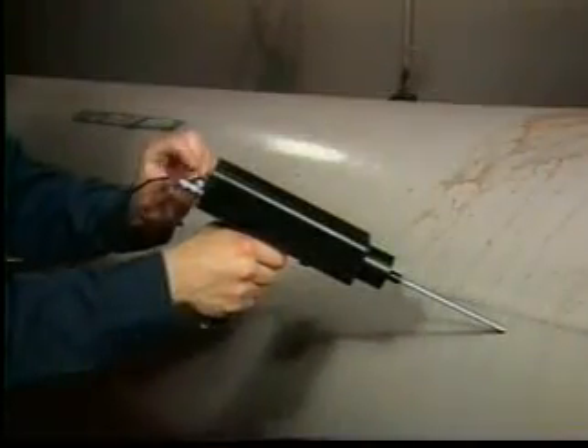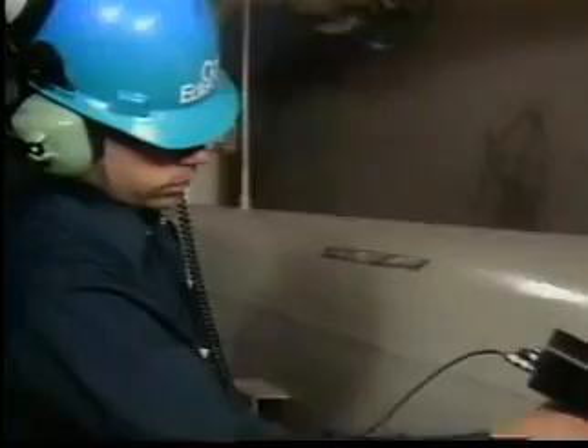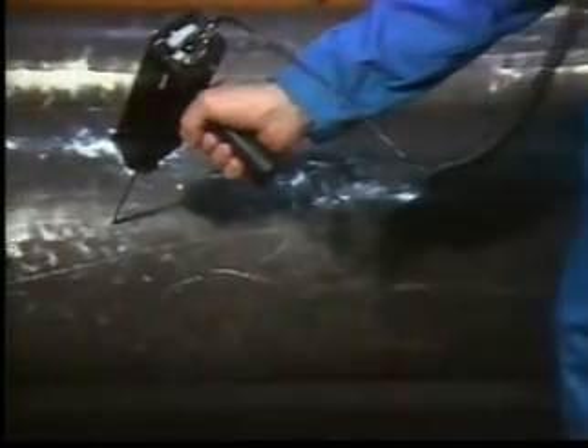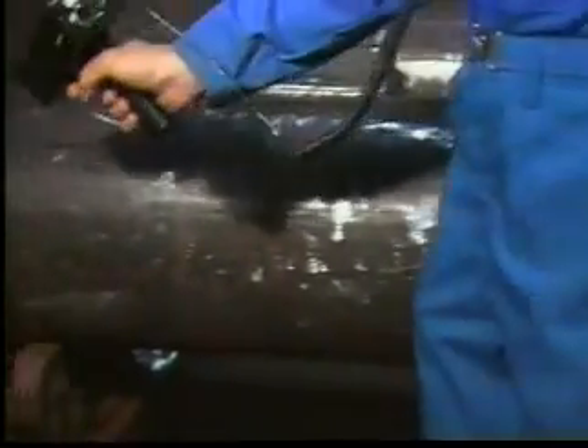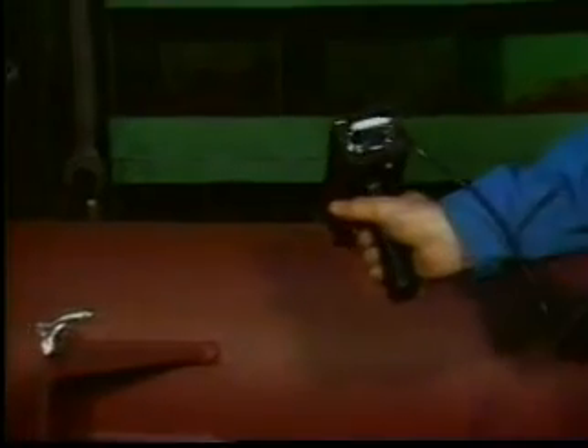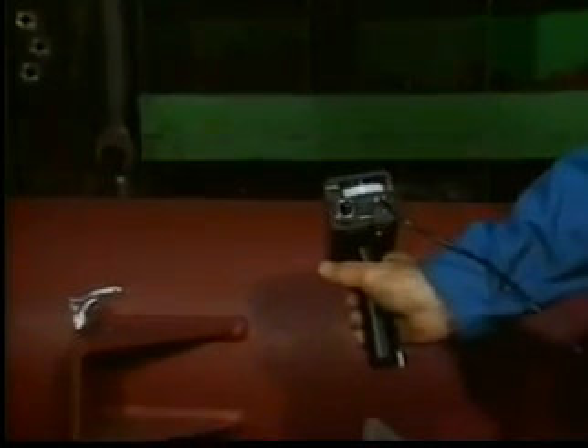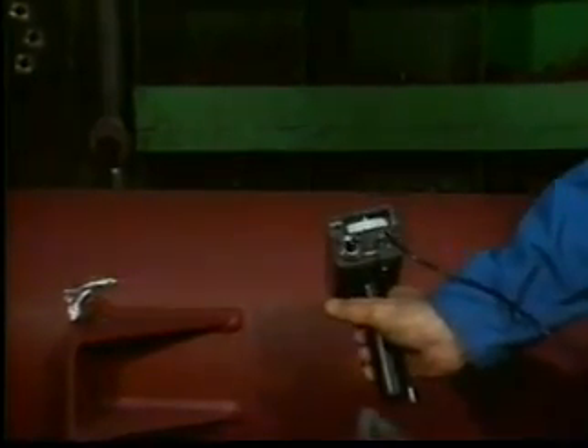To check for potential tube leakage, the contact probe is used to listen through the shell wall. Create four equal test zones. Touch the shell in each zone on both sides, listening for normal turbulent flow in the heat exchanger. A leak will be noted by a change in the turbulence. This will normally make a popping or crackling sound. If you're unsure about what you're hearing, compare the sounds with those of other heat exchangers in a similar area with similar load factors.